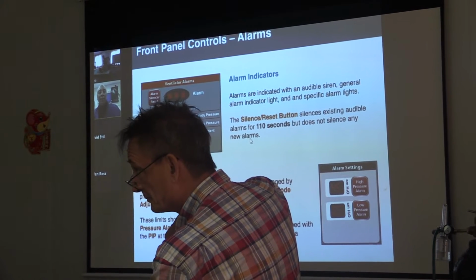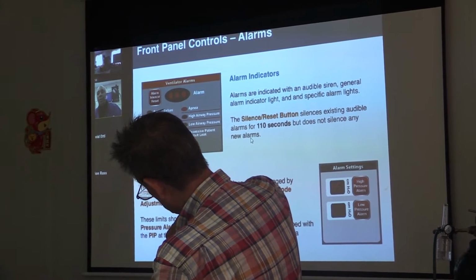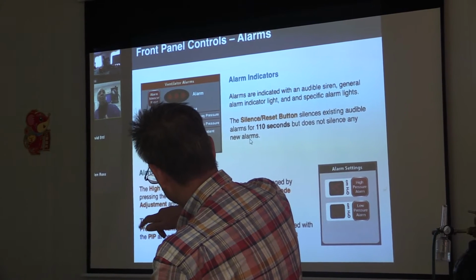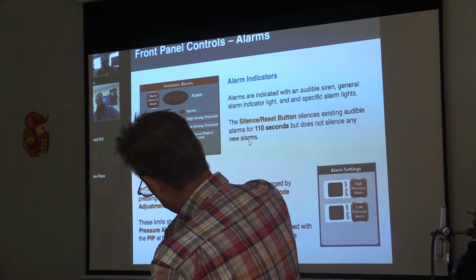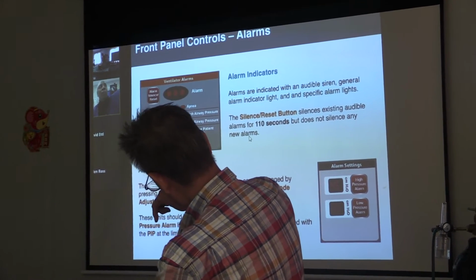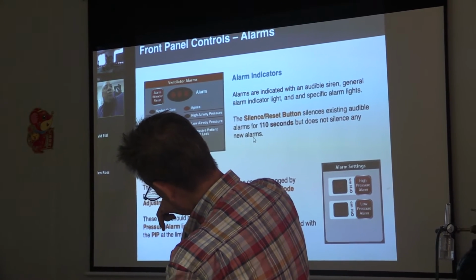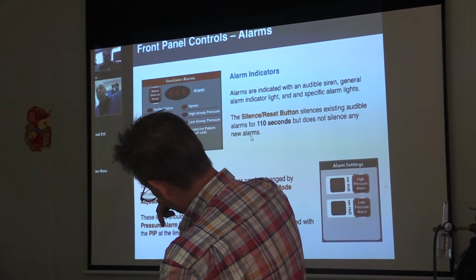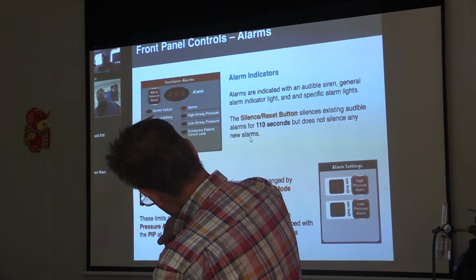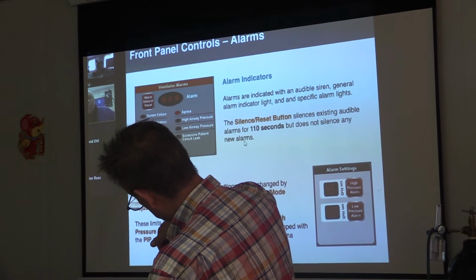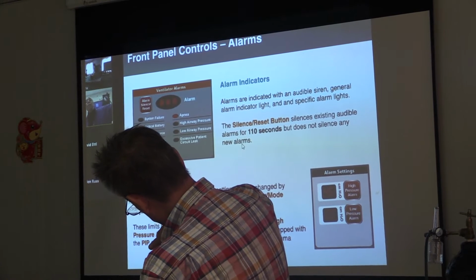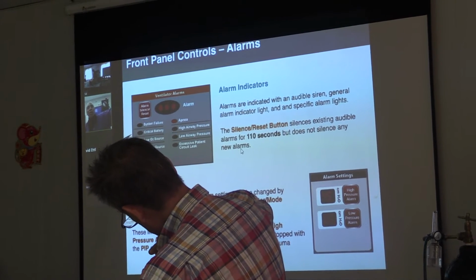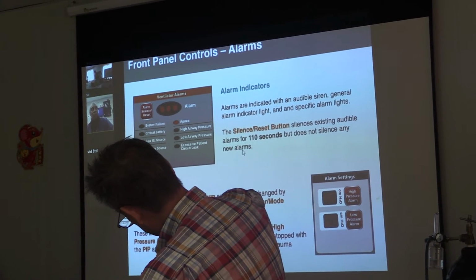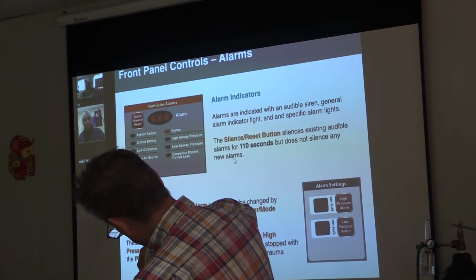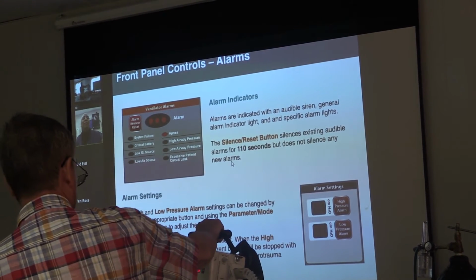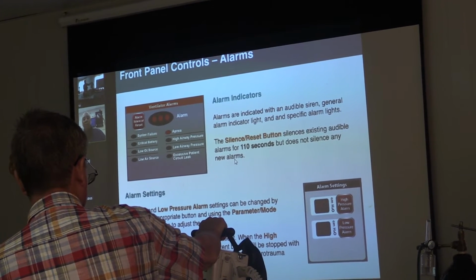So in that case, what you would do is make sure that there's no obstruction, and the patient's breathing okay, but the machine is alarming. You would go ahead and change the high pressure alarm by pushing the button, going to where it says parameter, and changing that to maybe 40 centimeters of water alarm pressure. Set it to at least 5 centimeters of water above what the patient is normally doing, and then the high pressure alarm will stop alarming, because it will be set at an appropriate level for that patient.